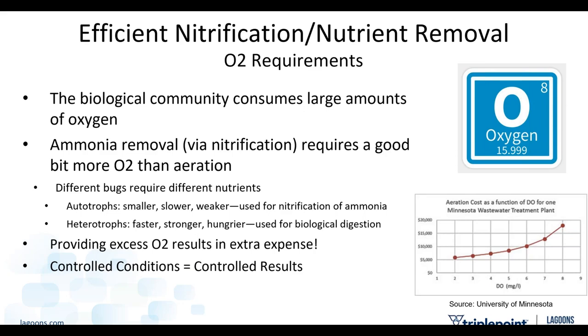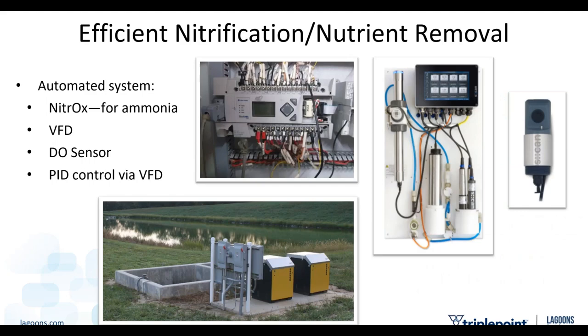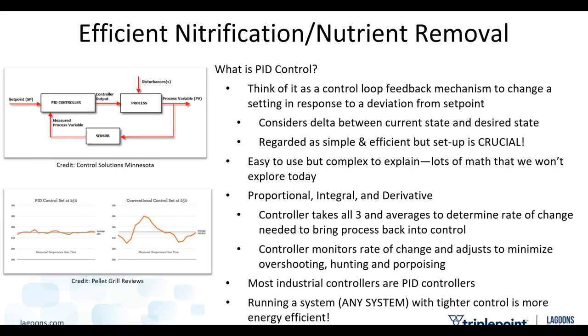Controlled conditions yield controlled results. Along those lines, automation is very, very helpful as well. Nitrox for ammonia is our product. The VFDs with DO sensors, and then you establish PID control. And you're ramping the blowers up and down in response to the amount of oxygen that's being consumed. Great way to right-size your aeration, right-size your energy bill at the same time. And PID control is such a neat topic. We could spend a couple hours on this, but I want to call out a couple of things here.